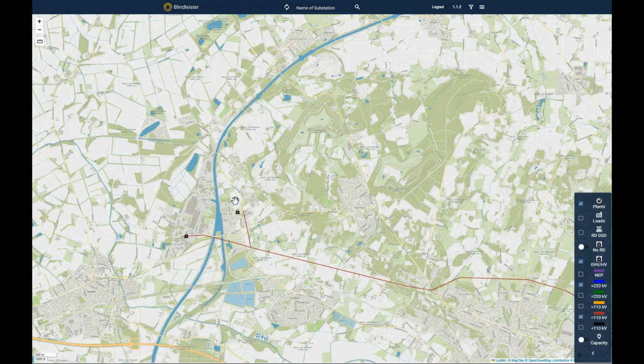If we make a grid connection request, the system operator will look at how much generation is affecting this network area, what the load is, and whether it exceeds the limit of this power line, also if the battery is injecting energy. And if yes, then it's rejected. So it's not a good area to request, for example, 40, 50, 60 megawatt or more of battery size.